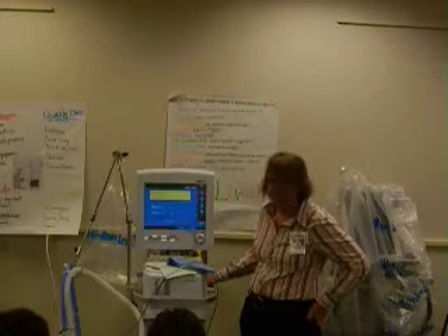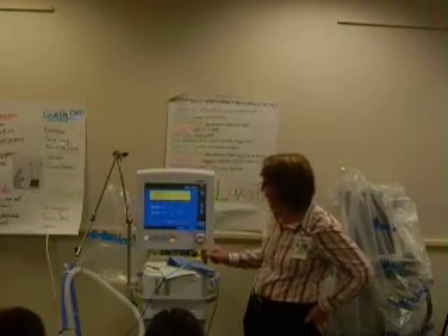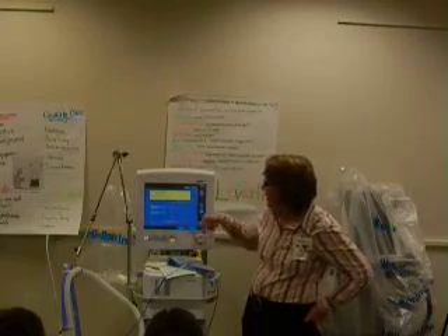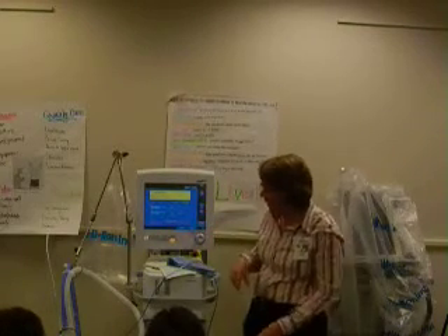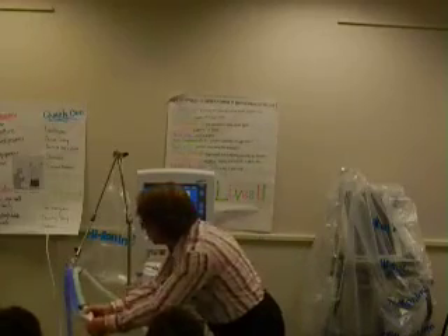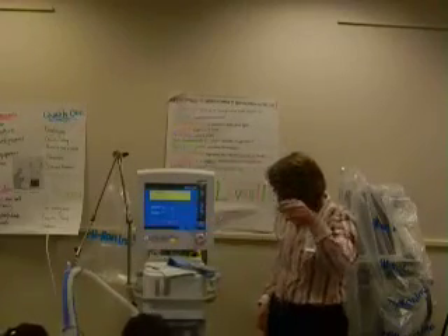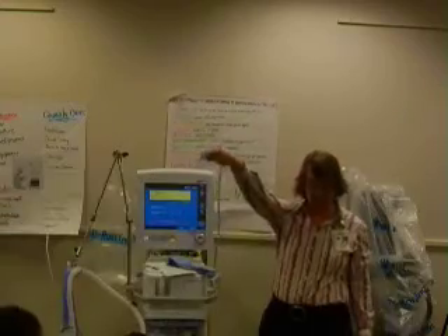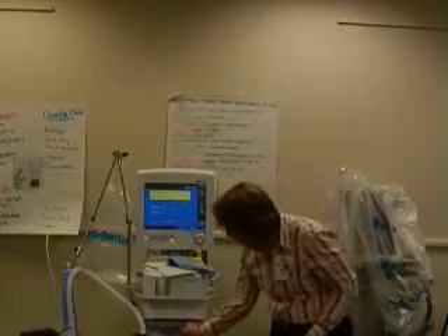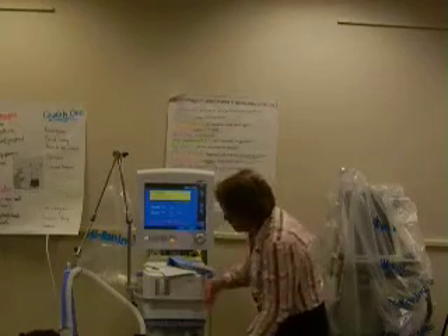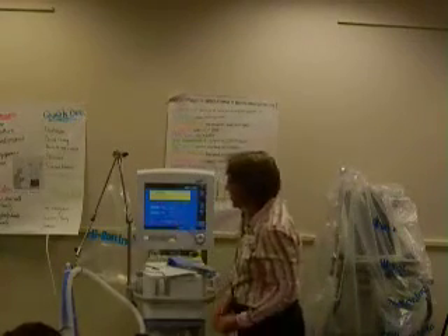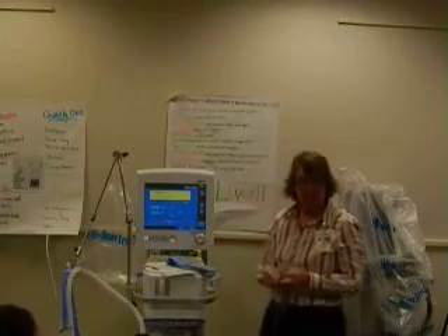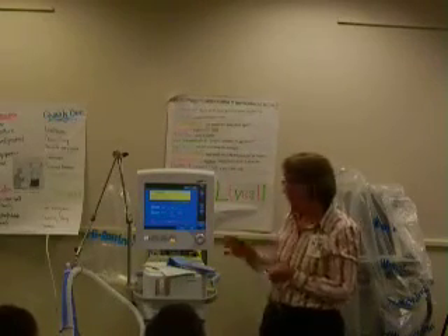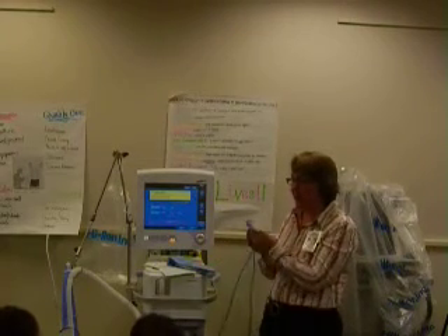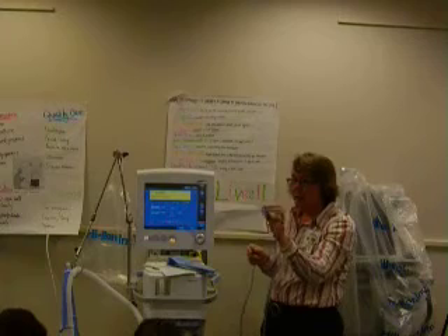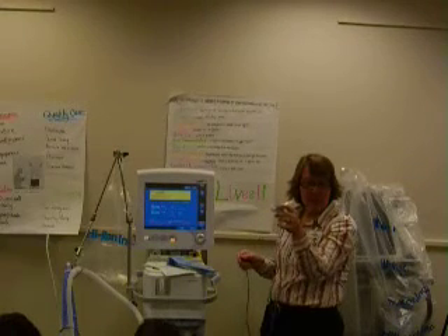Then it'll come up to this screen at standby. No ventilation delivered, and then you can set a few settings here if you want. Unique to this vent is the flow sensor. You must have this in order to run it. Without it, it won't work. It's an external sensor that goes at the patient Y to sense flows and pressure, so it's a lot more accurate than one sensing all the way back at the ventilator, because we're sensing at the patient's airway. Most vents don't do it like this anymore, but some still do.